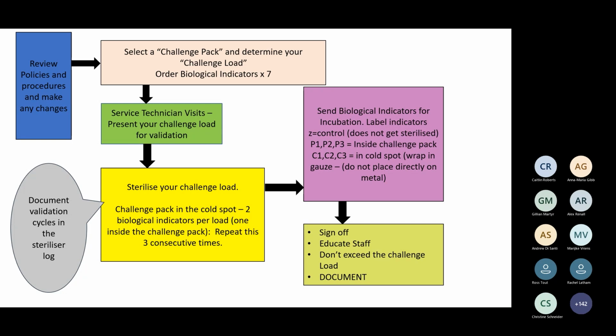Then your service technician is going to visit. You're going to present him with your challenge load for validation. He's going to do the process. He's going to sterilize your challenge load. He's going to put the challenge pack in the cold spot after the cold spot of the machine is identified. And then you're going to process your biological indicators per load, one inside the challenge pack and one in the cold spot. You're going to do that in 3 consecutive cycles, either at the time of validation or immediately after.